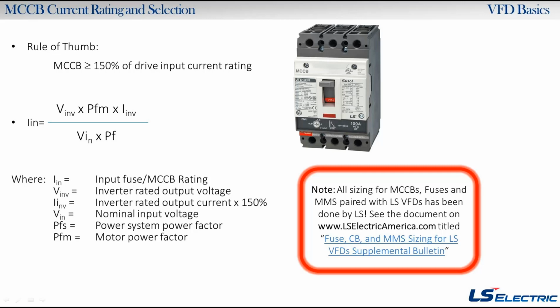You could also use a more complex formula, which uses the inverter rated output voltage. Then it looks at the power factor of the motor and of the system, which is PF on the bottom, the input current, and the input voltage, and then you can calculate how much you need to rate your fusing or your circuit breaker for. I also mentioned you may want to check your local code and see what they recommend as well, because we don't want to go against that. That's going to change based on region or state or municipality and all kinds of fun stuff.